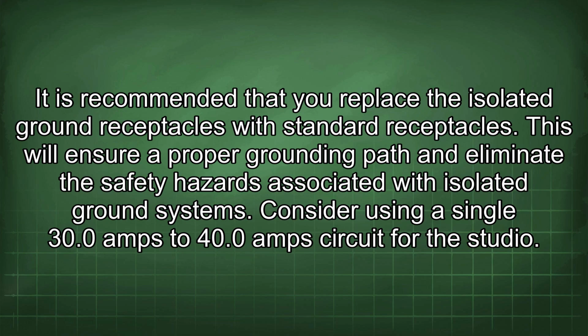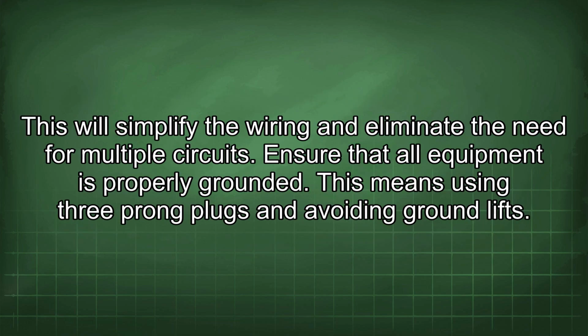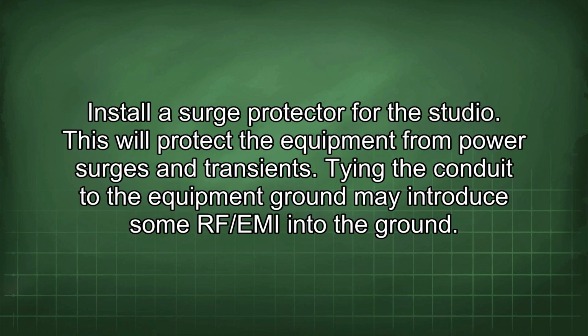Consider using a single 30.0 amps to 40.0 amps circuit for the studio. This will simplify the wiring and eliminate the need for multiple circuits. Ensure that all equipment is properly grounded. This means using 3-prong plugs and avoiding ground lifts. Install a surge protector for the studio. This will protect the equipment from power surges and transients.